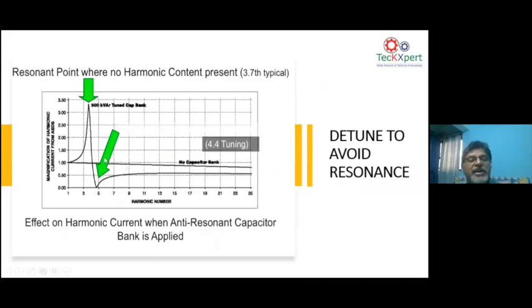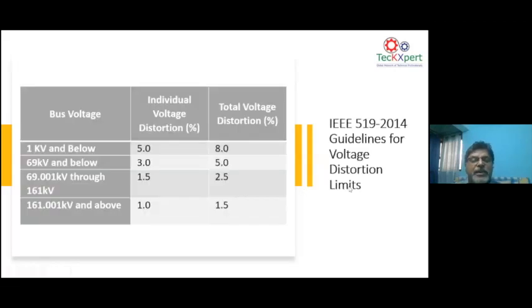Now you can see when you put a detuning reactor, for example, here you are putting a 4.4% detuning reactor. By putting that, you are making sure that the resonance point of the branch, the natural frequency or resonant point of the capacitor reactor circuit, is shifted between 3 and 5. So there is no resonance at that point. So by doing that, you are detuning the capacitor to avoid parallel or series resonance. This is how the function of detuning comes in.